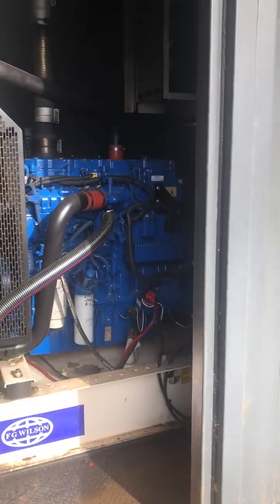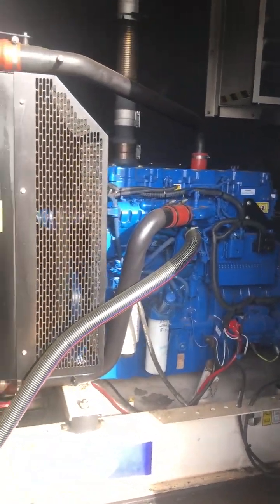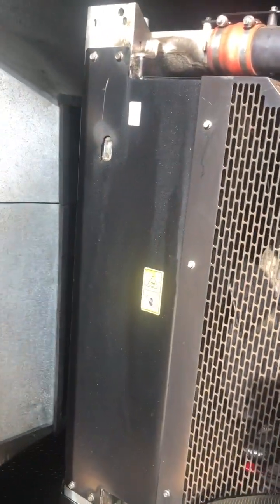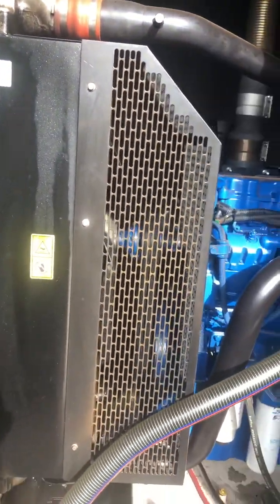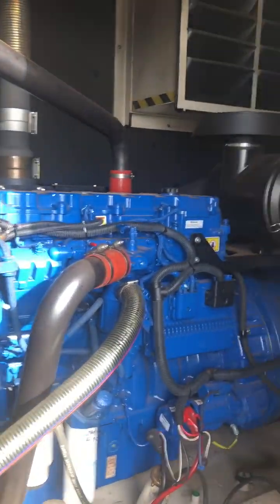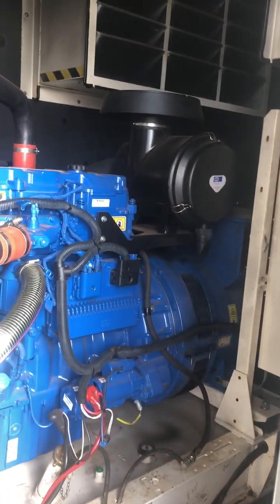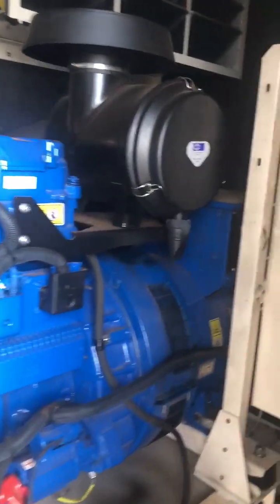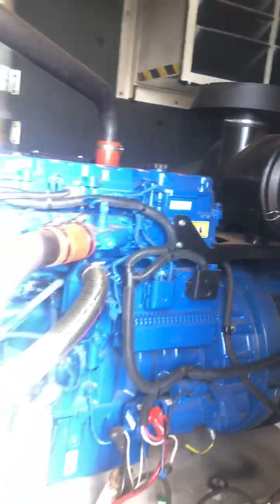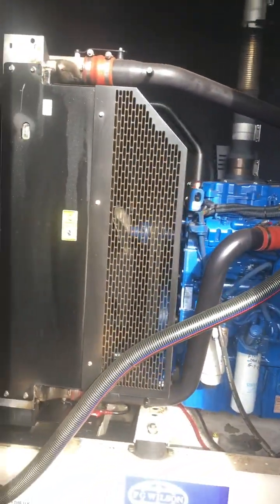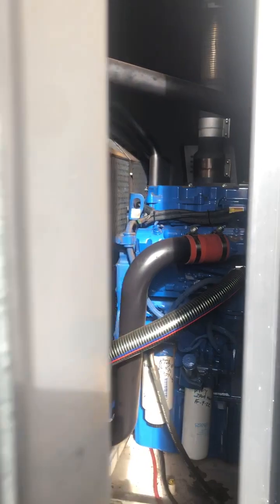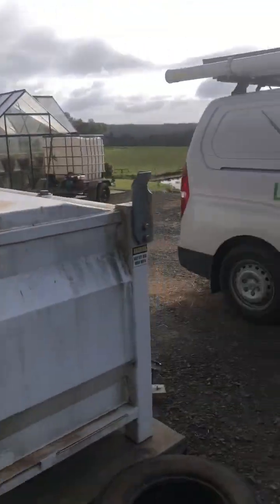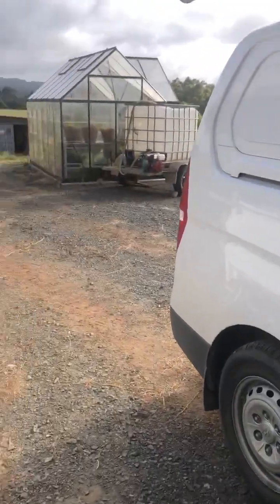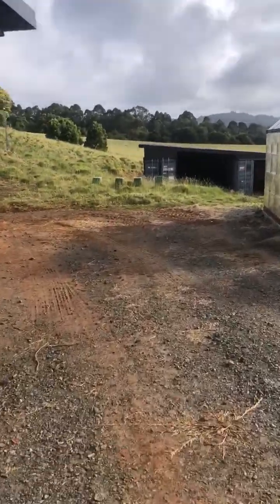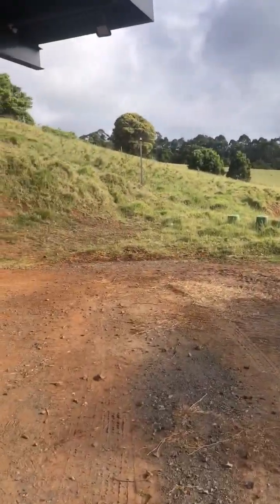Here, inside, is where the backup diesel generator is. It's quite a large generator, normally about 180 kVA. Normally you wouldn't need anything quite so big, but this site has some fairly significant loads at different times of the year, so it may be called into use. So we'll just go around to the battery end of the container.